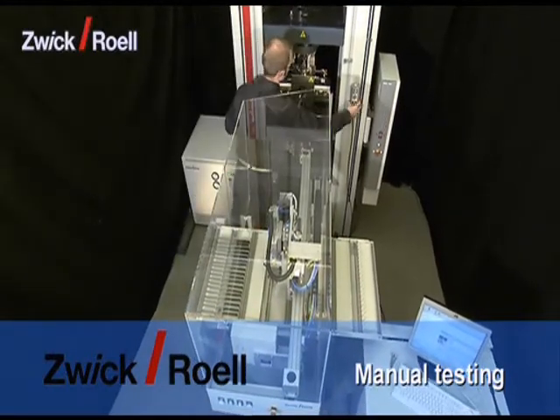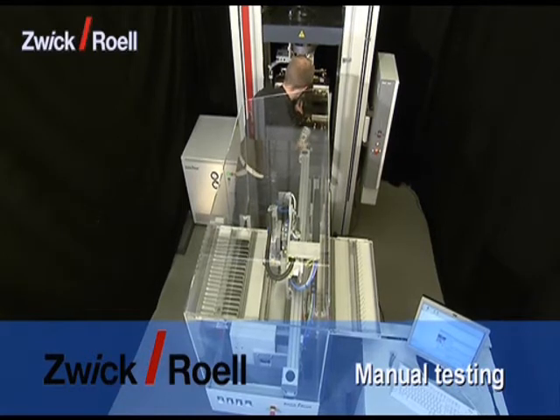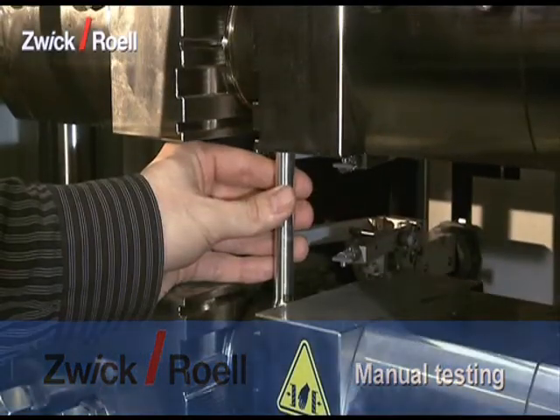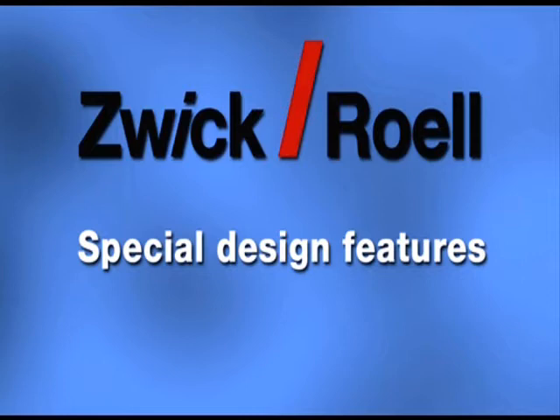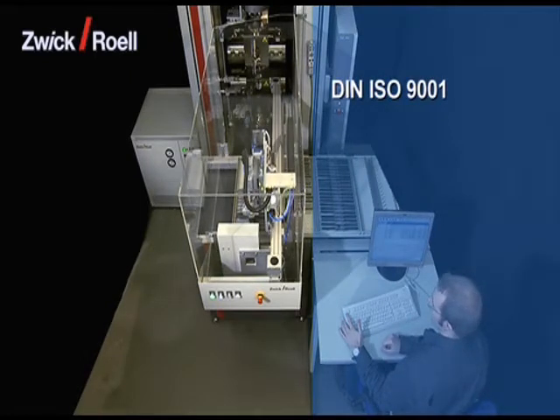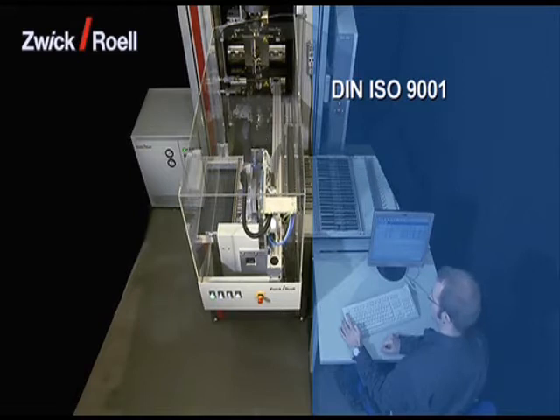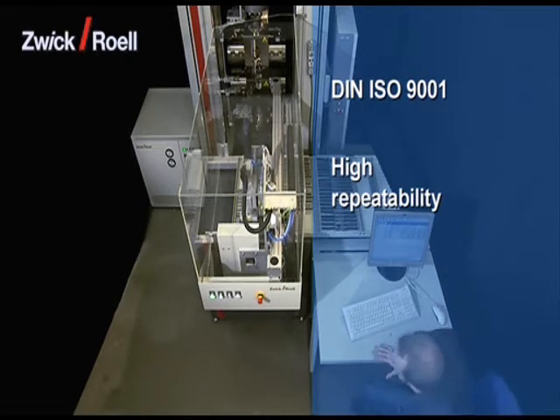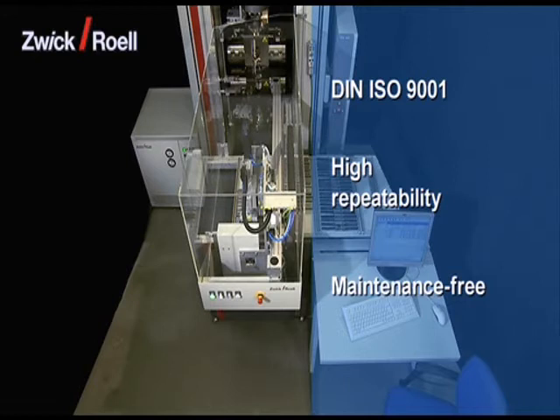The test area is then optimally accessible from the front. As the testXpert software is used both for manual as well as automatic operation, there is no need for retraining. The traceability of the test conditions according to DIN ISO 9001 is ensured. As there are no influences caused by the operator, such as hand temperature or inaccurate placing, there is a very high repeatability of the test results. The use of reliable and proven standard components made by Zwick and other well-known suppliers means that the unit is virtually maintenance-free.